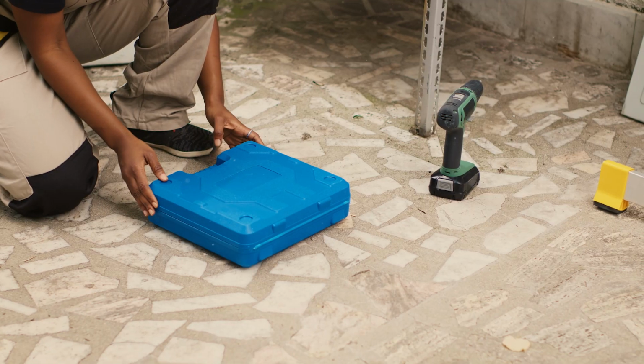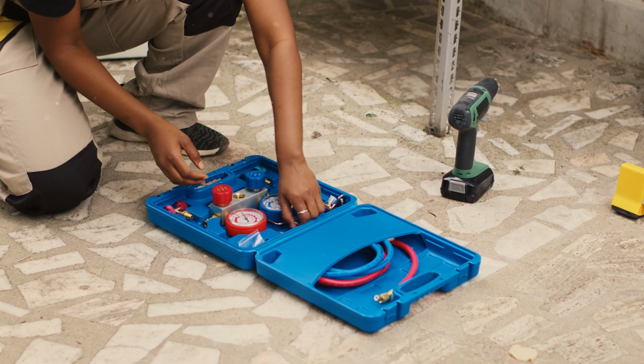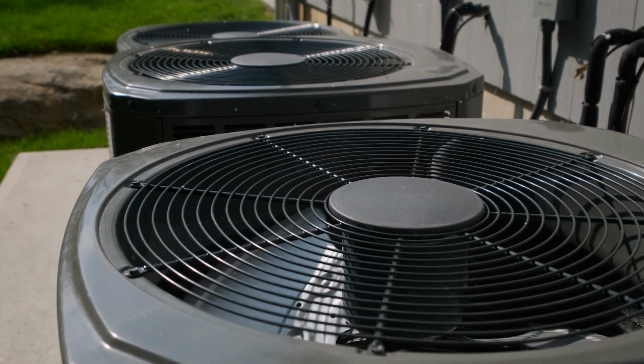And of course, the steps to address it if you have a dirty system: make sure you hire an HVAC technician or an inspector. They can at least tell you if it's bad or really contaminated. Do a duct cleaning. People charge maybe a couple of $100 to get your ducts clean. As soon as you get in there, unless they put in new air filters, put the new ones in yourself. Clean the coils and components. You should be doing that every year anyway. Seal your ducts. Ensure that the ductwork is properly sealed to prevent future contamination. This involves using a mastic sealant or metal tape to seal joints and connections. And implement a great maintenance schedule.